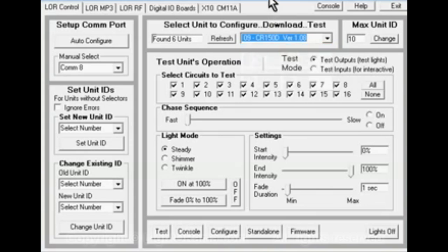And so what this means is the computer has a way of telling the USB adapters apart, and this COM number will follow the adapter. It doesn't matter which USB port you have it plugged into, the same COM number will be associated with that particular USB 485 adapter.